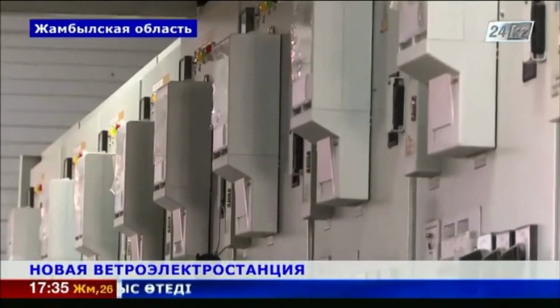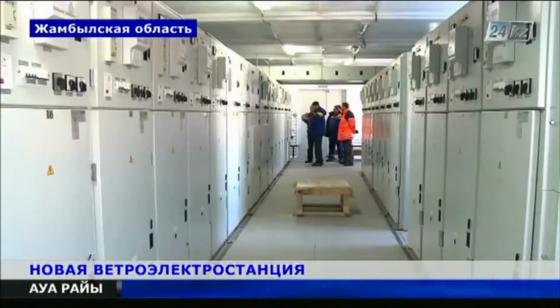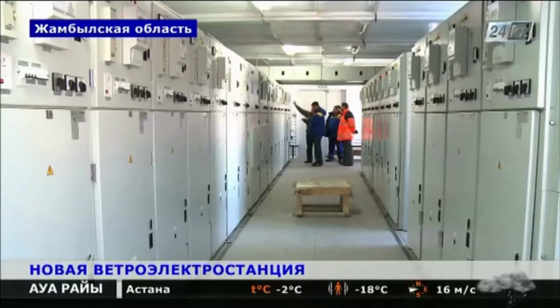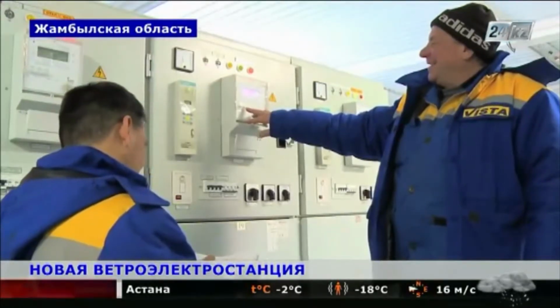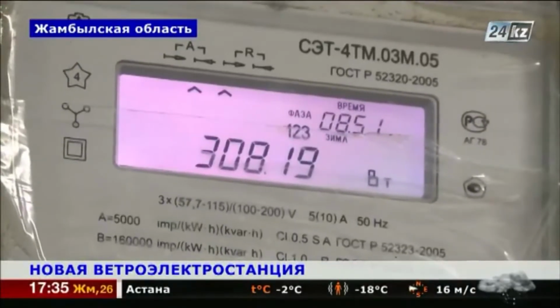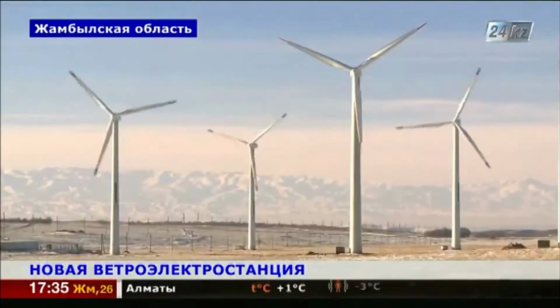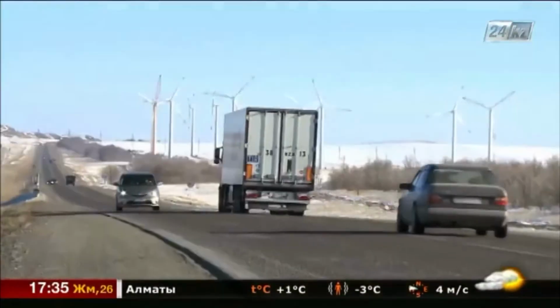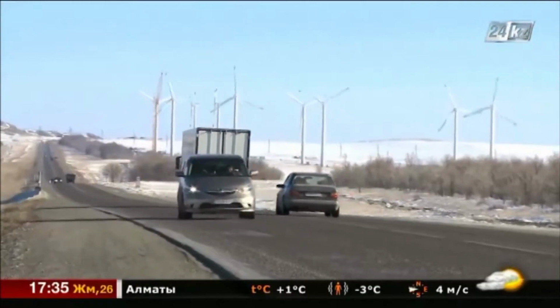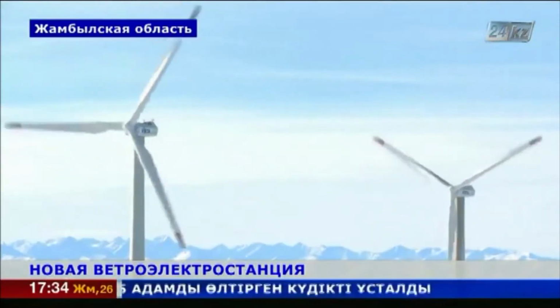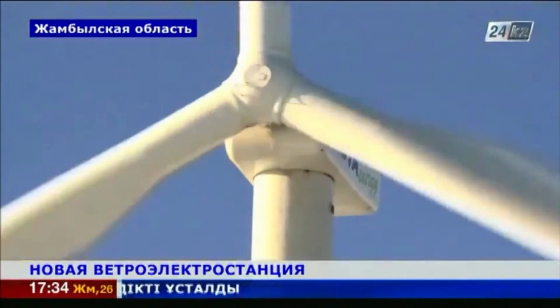In addition to the wind power plant, a 110/10 kilovolt high-voltage substation, Kordai wind farm, was built with 2 transformers of 16 megavolt-ampere each and 2.4 kilometers of 110 kilovolt transmission line connecting to the power system. Next to each wind turbine, a 10/0.69 kilovolt KTP unit was allocated.